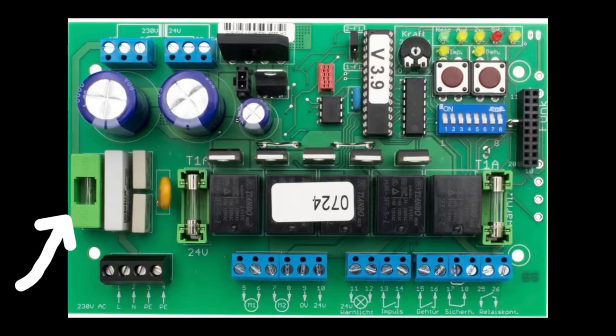Fuse. This is main supply line fuse, AC 230 volt for terminals 1 to 4. Fuse is 1 ampere. Fuse will slow blow. This fuse power supply output DC 24 volt for terminals 9 and 10.